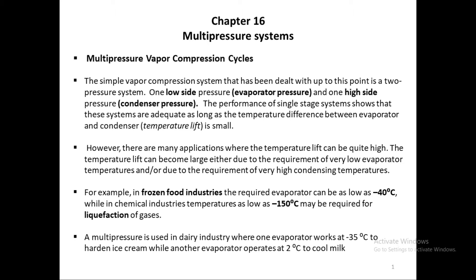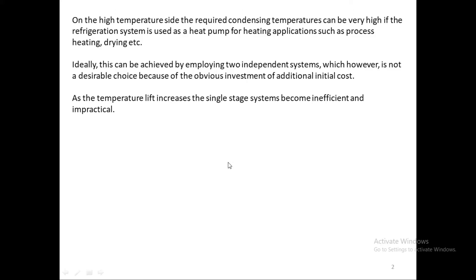For example, in the dairy industry you need one evaporator at minus 35 degrees centigrade to harden ice cream and another at 2 degrees centigrade to cool milk. Ideally this can be achieved by employing two independent systems, but that is not desirable because of the higher initial cost. As the temperature lift increases, the single-stage system becomes inefficient and impractical.